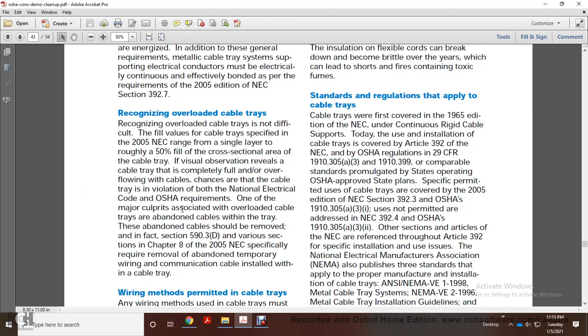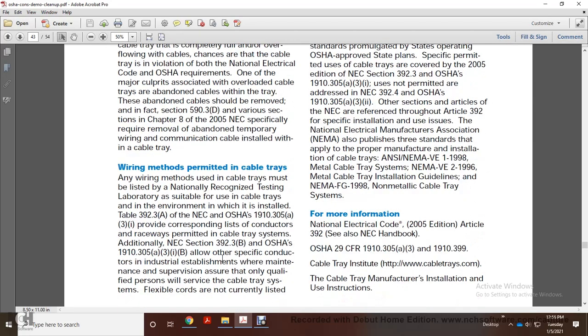and OSHA requirements. One of the major culprits associated with overloaded cable trays is abandoned cables left in the tray, but abandoned cables should be removed. In fact, Section 590.3(D) and various sections of Chapter 8 of the 2005 National Electrical Code specifically require removal of abandoned and temporary wiring and communication cable installed on the cable tray.